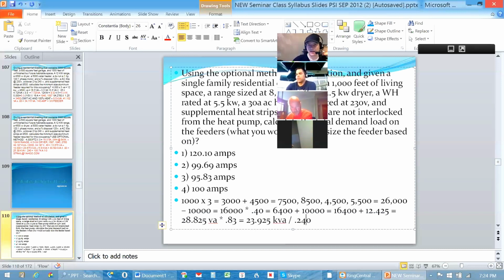If I lost anybody, speak up and I'll certainly go back and reiterate. Yeah, I got a little turned around. I had the 16,400. I'm getting a little confused going back and forth with the decimals, sometimes 8,500 and sometimes 8.5. Let me go back and change that, because that's a fair comment. The method I use is to turn them all into kVA values because it's easier for me to keep them that way, but when I'm writing them down like this, I should just write them all out the same way. These are all going to be just VA values, not kVA, so there wouldn't be any confusion.